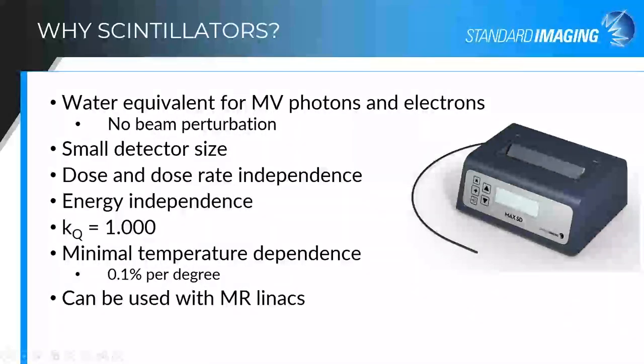One of the first questions usually asked about scintillation detectors is why would I want to choose this over something else that's available? The major advantage of scintillators is that they're water equivalent for both megavoltage photons and electrons. The key point is that you're not changing the radiation interaction right at the point of measurement, and then having to do additional corrections for that perturbation. They can be made very small, so they're useful for small fields in that you're measuring over a very small physical area.